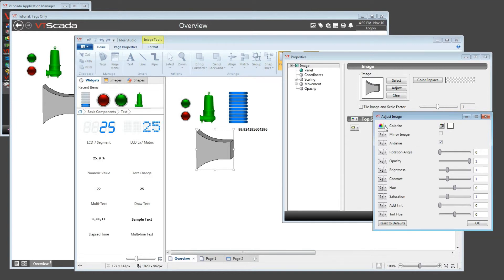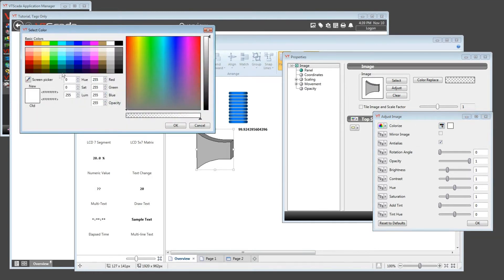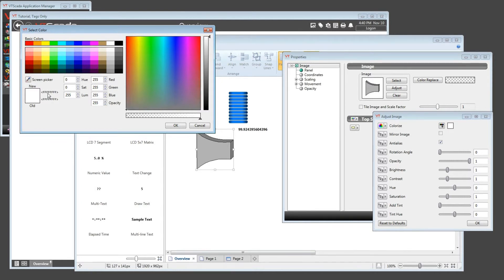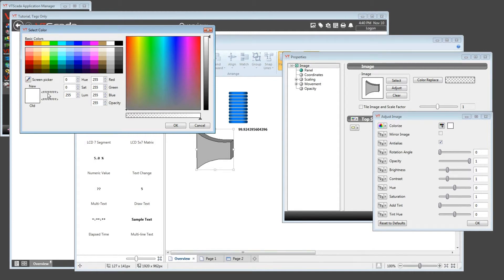Now, with color, it's a bit more tricky because color tends to use these RGB values that are in hexadecimal notation. Now, fortunately, there's also an older system built into VTScada where color numbers can be numbers, but they've got a value from 0 to 255. So if I were to look up the old palette in the help file and choose values from 0 to 255, that would allow me to sort of, kind of, use a tag value for color.